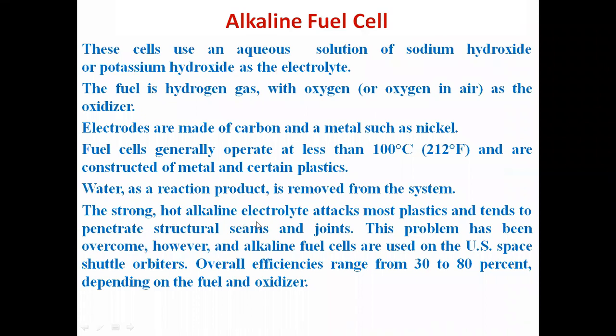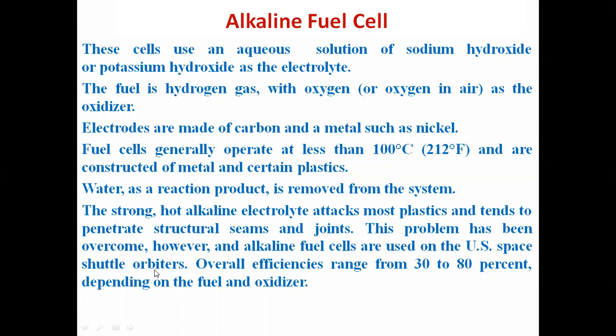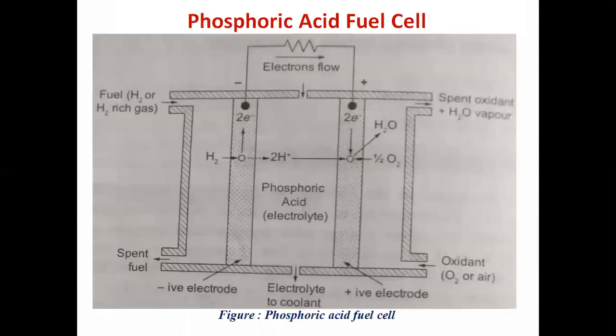The strong hot alkaline electrolyte attacks most plastics and tends to penetrate structural seams and joints. This problem has been overcome, however, and alkaline fuel cells are used in the US Space Shuttle orbiters. Overall efficiency ranges from 0.3 to 0.8, that is 30 to 80%, depending upon the fuel and oxidizer. If pure hydrogen and pure oxygen are used, efficiency will be higher; if hydrogen-rich gas or ambient air is used, it will be lower.